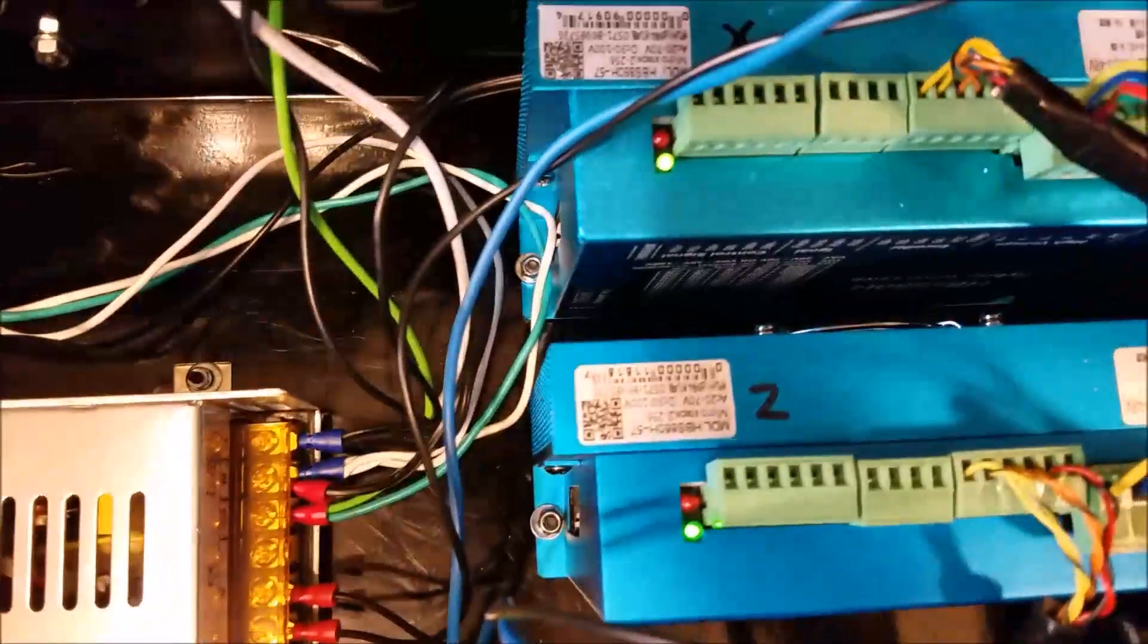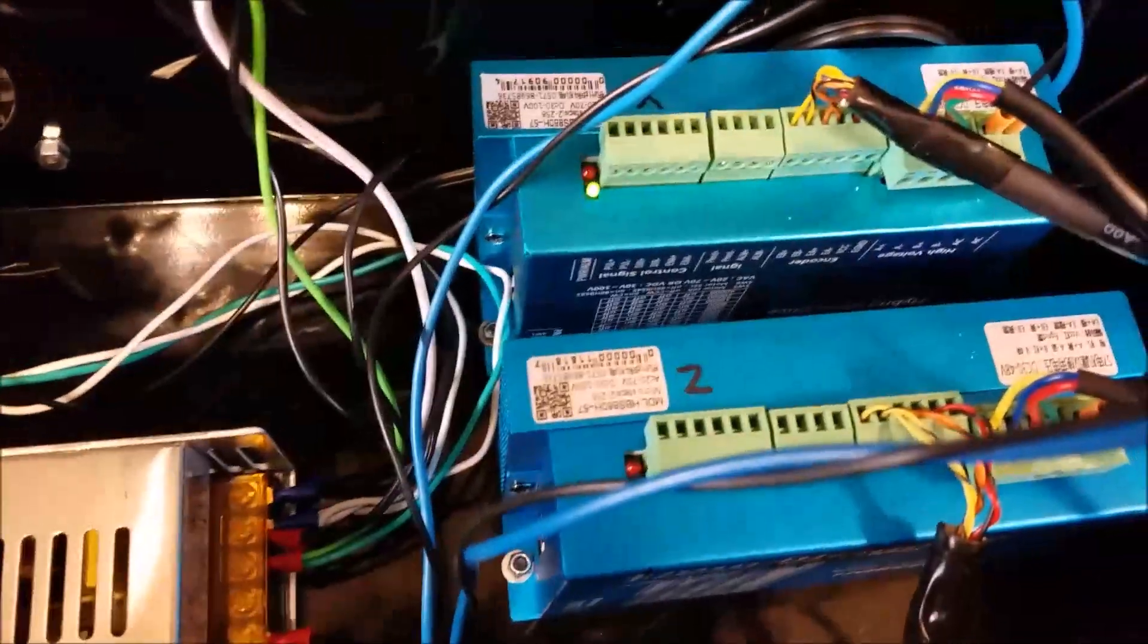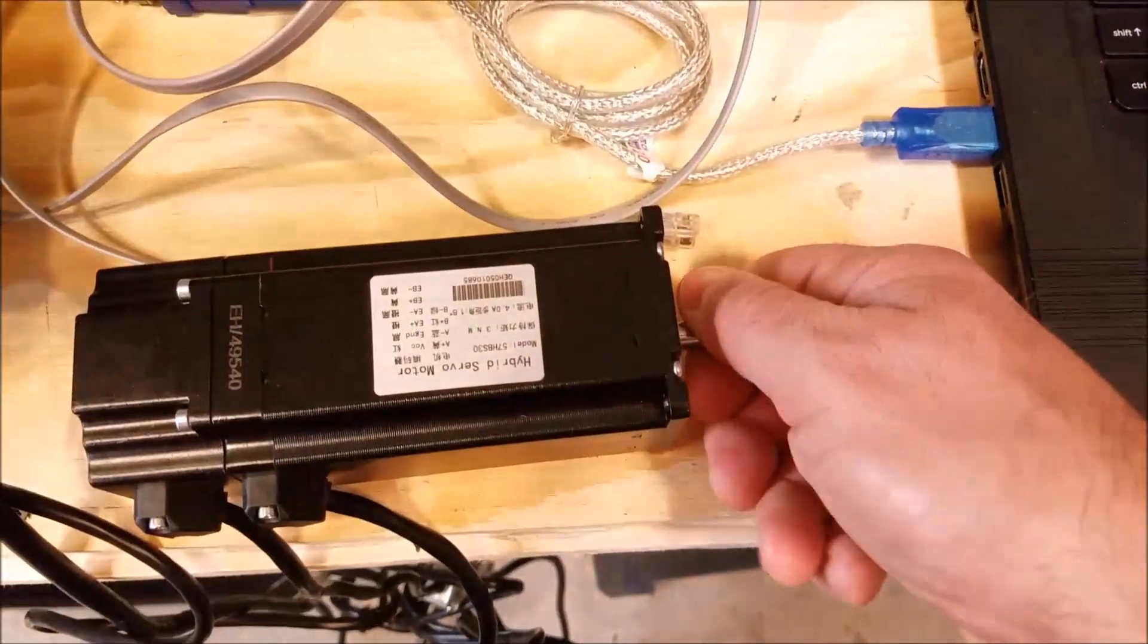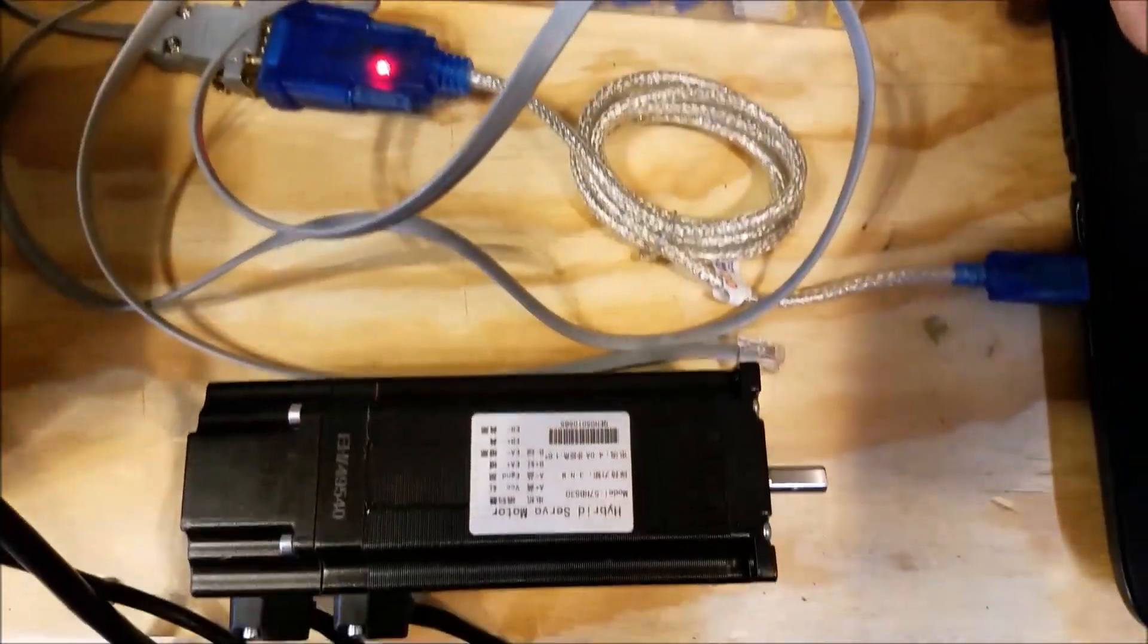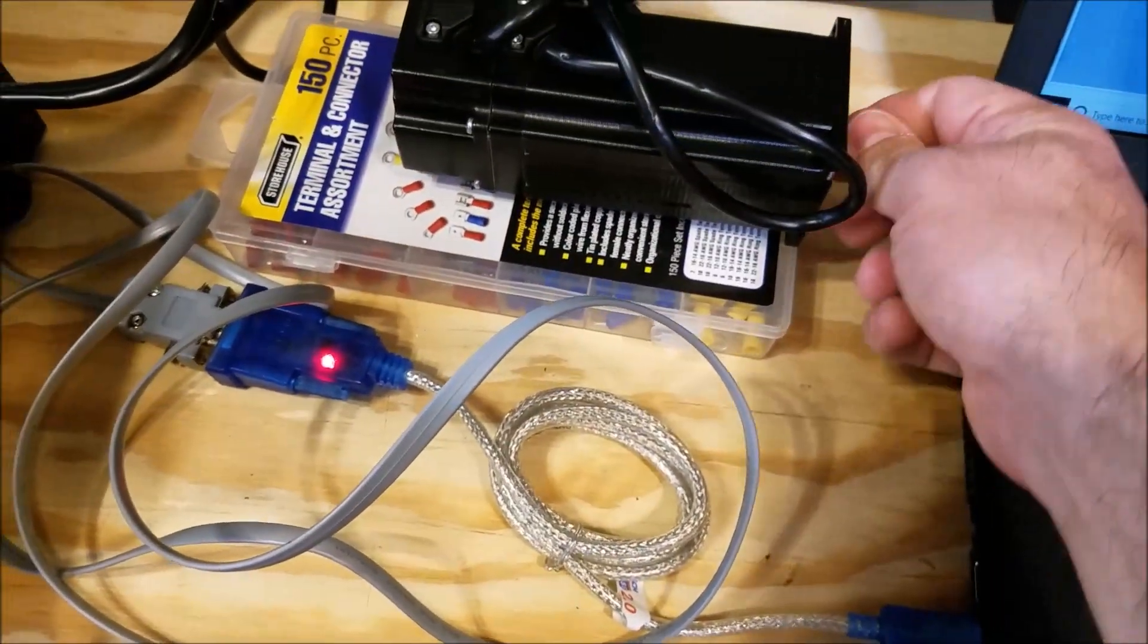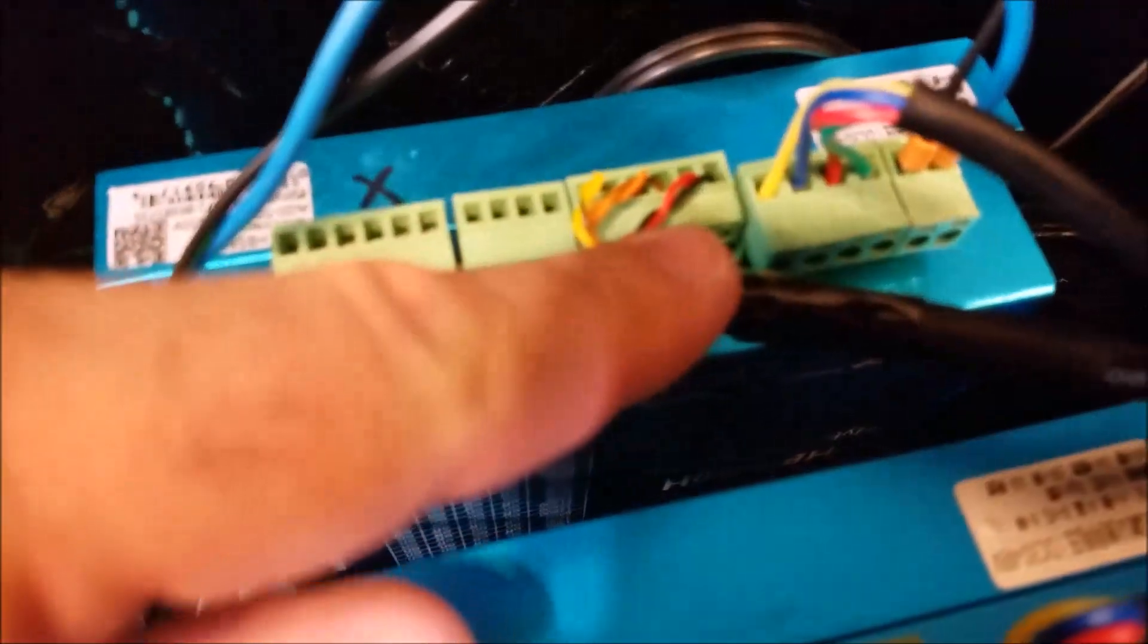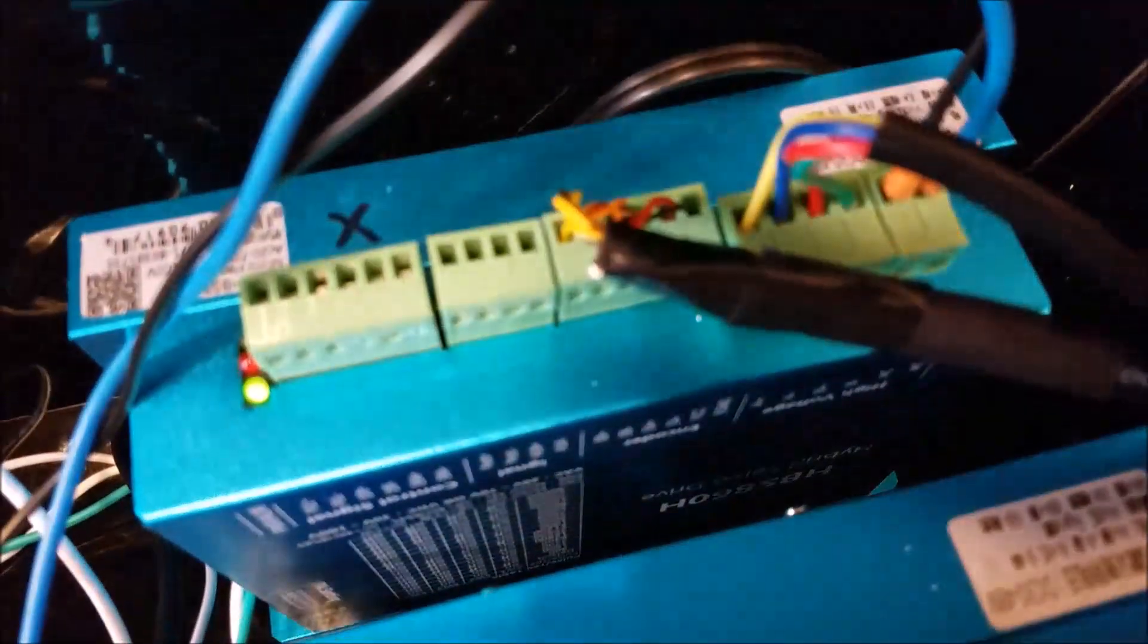If you run into a situation where you power it on and the light's blank or something just doesn't seem quite right, if you check your motor shaft and a motor shaft isn't locked up like it spins freely, even though it's powered on, shut it off immediately and check all your wiring because you probably connected something wrong.